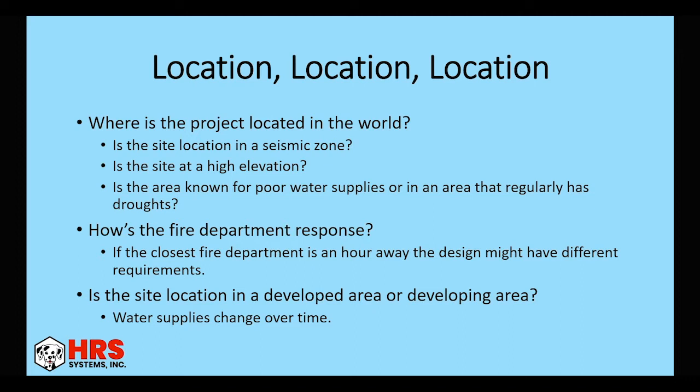This could determine your water supply, as well as whether your sprinkler system is heavily going to be relied upon if there is a fire. Like I show here, if it's an hour away, your system might have to be more robust. Is the site located in a developed area or developing area? If it's in a developed area, your water supply isn't going to change as much potentially in the future. It can still change, but it won't change as much. Whereas if you're developing in a new area, your water supply could drastically go down as more occupancies and facilities are coming in and drawing more water away from the supply. These all need to be considered when you're looking at a potential pump. Then is your water supply changing over time? If you can get some of that data over years, that's also very helpful, but not very common to be able to get.